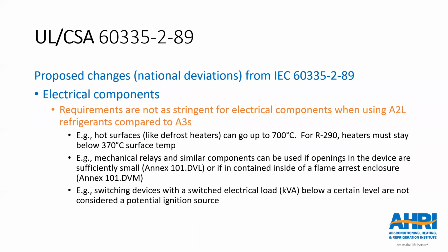So furthermore, based on research conducted on A2L refrigerants in recent years, the requirements for electrical components are not quite as strict when using those refrigerants as opposed to using an A3 like R290. Hot surfaces when using an A2L are limited to 700 degrees C as compared to 370 degrees C for R290, so that's a pretty big difference.